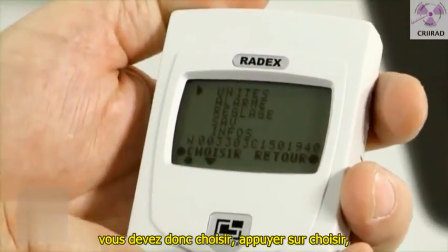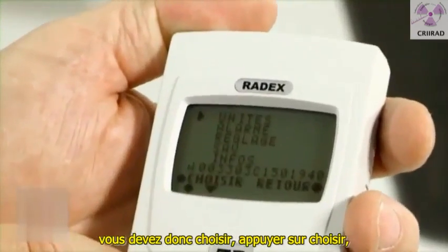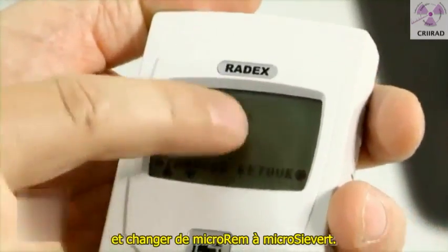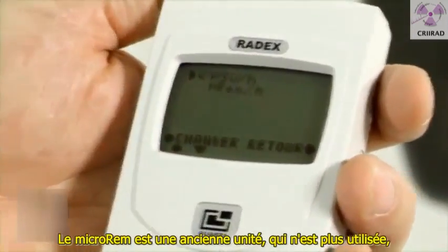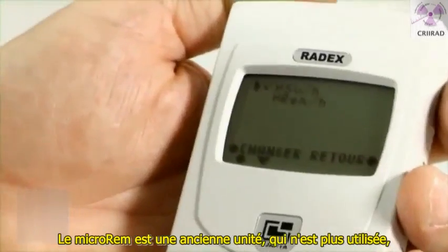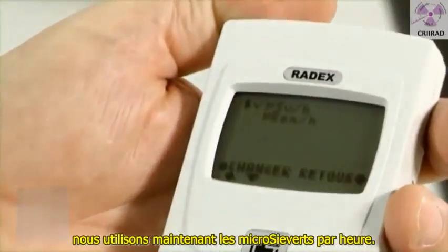You would have to press the button, choose, and change from micro-REM to micro-sievert. Micro-REM is an old unit which is never used anymore. Now we use micro-sievert per hour.